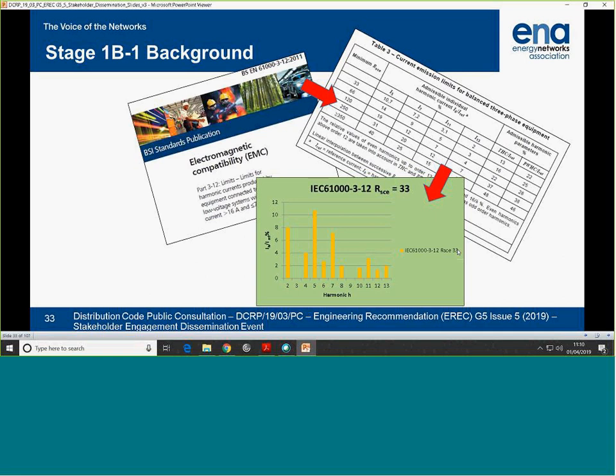Someone who's familiar with this standard, and there may not be, I don't know who exactly, but basically it has some tables of limits, and if you look at this, the column called minimum RSCE is a ratio of short circuit fault level to the rating of the equipment, so a measure of the strength of the network. And this row, RSCE of 33, up to a voltage change of 3%. If you went no load to full load, if you had a system that was that strong, you'd have a 3% change in voltage. Relevant to the flicker and P28 document. In the UK, a lot of networks are designed with a 6% drop for a normal load, so that would be an RSCE of 16.7. Weaker network. So our networks are weaker than that assumes.